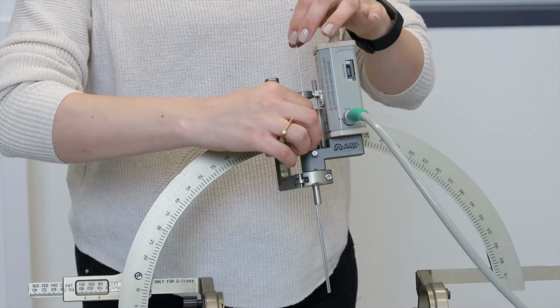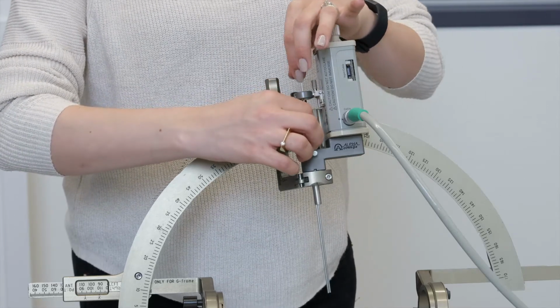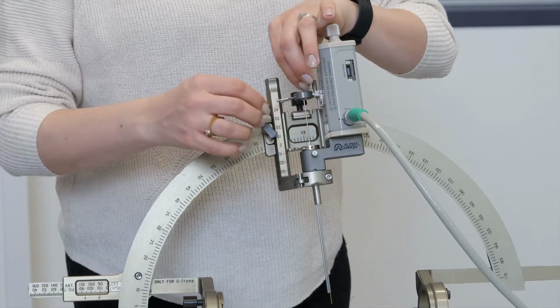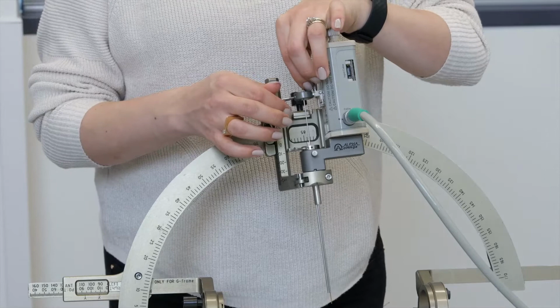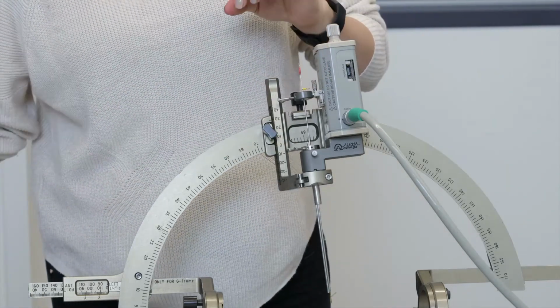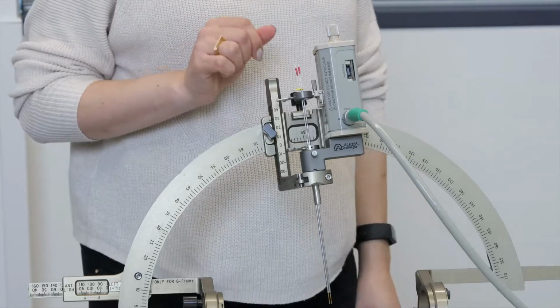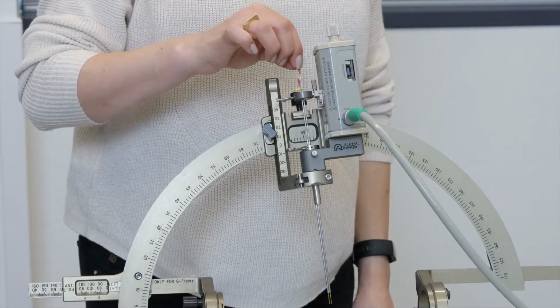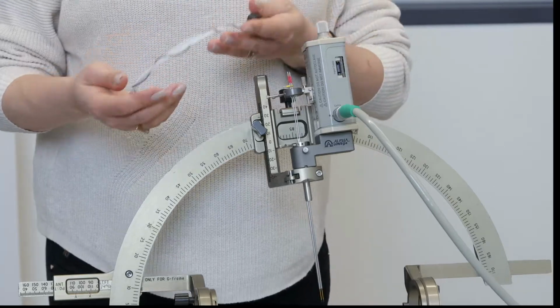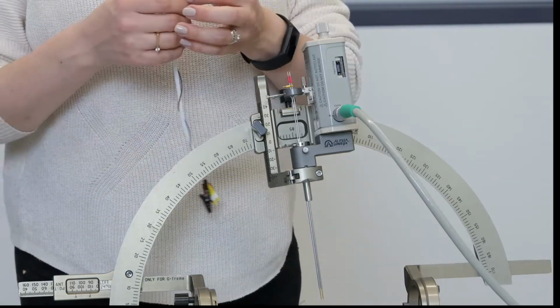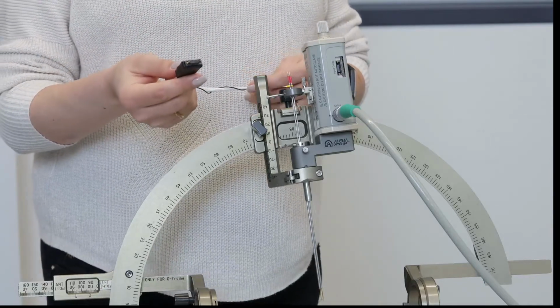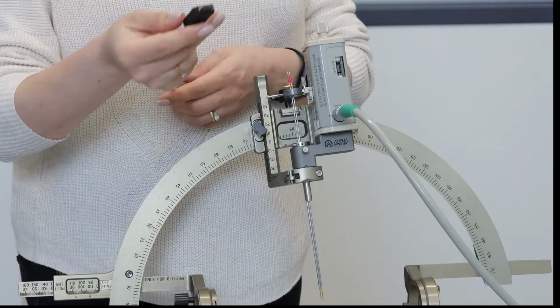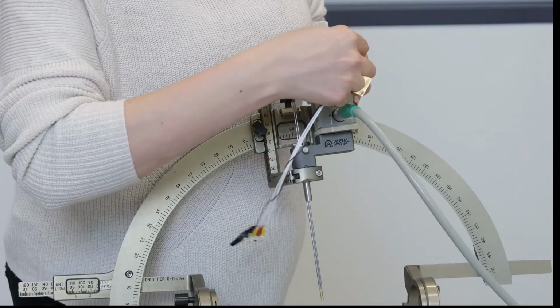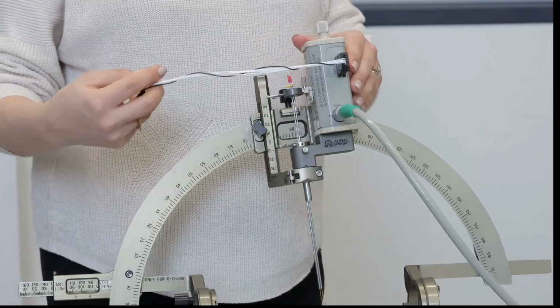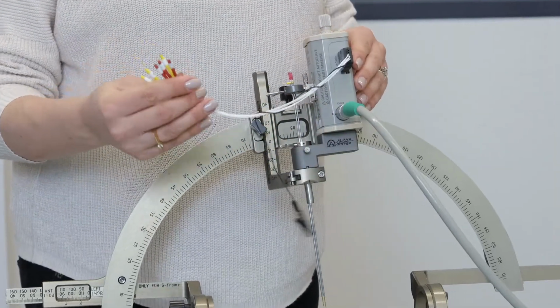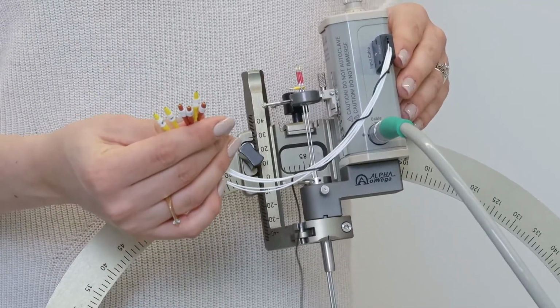Insert the neuroprobe all the way in the electrode holder, making sure it goes through the cannula as well. Tighten the screw on the electrode. Push the micro tip all the way down. Take the input cable from the sterile sleeve. On one side, it has a connector that connects to Alpha Omega's drive Headstage. The cable connector has a marker. The other side has single color-coded socket connectors.